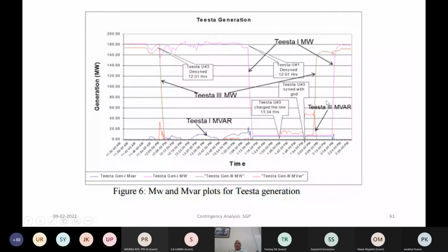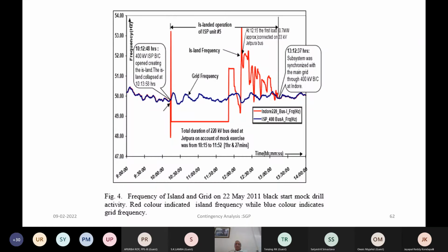Similarly, this is the active and reactive power control. So you can see the active power. This is the reactive power at the bottom. So this type of changes will have to be handled during black start operation. This is again the frequency, grid versus island frequency. You can see the grid. When you have restored, you have to synchronize back with the grid.